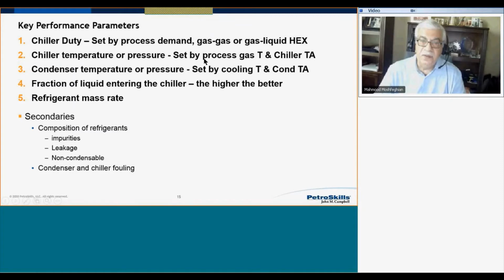So let's review some of the key performance parameters for minimizing power requirement. Chiller duty, as we saw, is set by the process demand, process temperature, as well as the gas or gas liquid heat exchanger that we utilize to minimize the power duty of the chiller. The next item of importance is chiller temperature or pressure. Again, this is set by process gas temperature and chiller temperature approach.